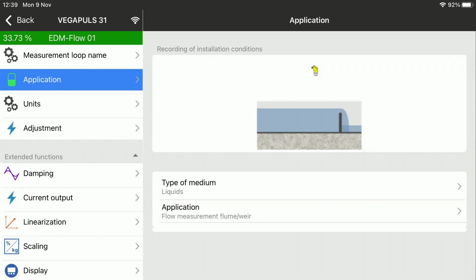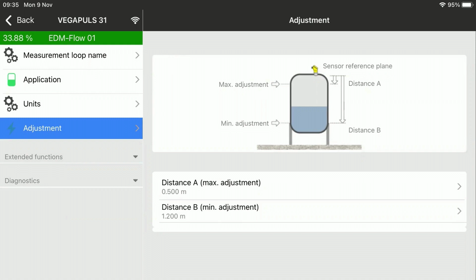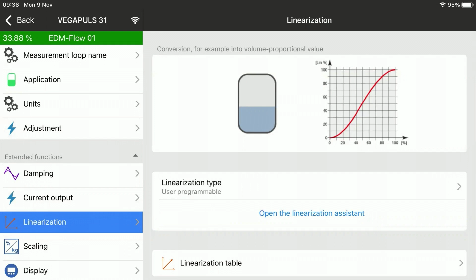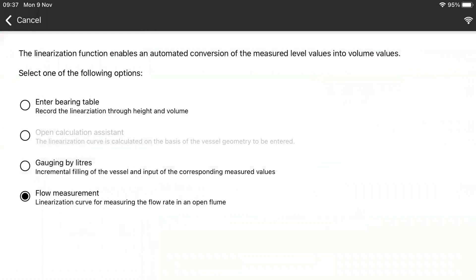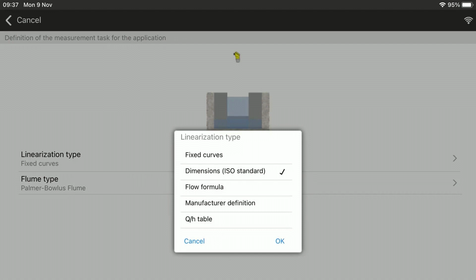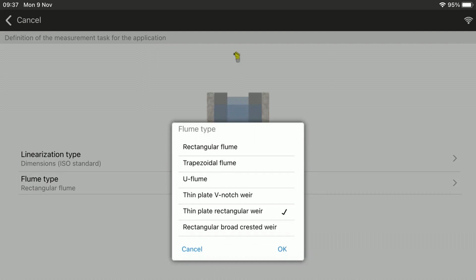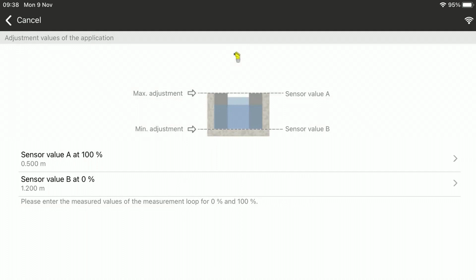So the app also gives you a graphical representation of the application as you move through the setup. So we can see that we're monitoring a flow in this case. The adjustment of the sensor is based on distance from the sensor reference plane, or the datum, which is the face of the sensor. So we set up our minimum and maximum distances. We can then go into a linearization assistant, or a setup wizard if you like, where we can step through the setup for a particular flow application. So we select flow measurements, and then it gives us a number of options, including the ISO standards, for flumes, for thin plate weirs, and also for broad crested weirs. So in this case, we can select a thin plate rectangular weir, and we can confirm our min-max adjustment.